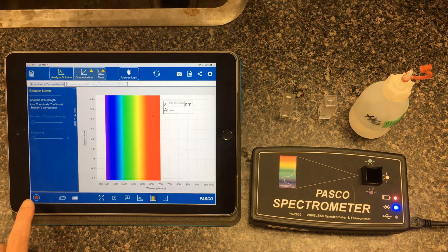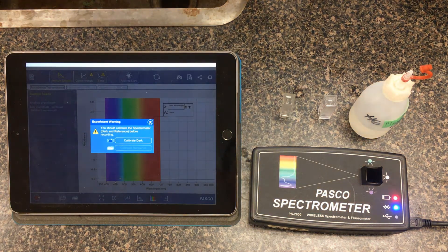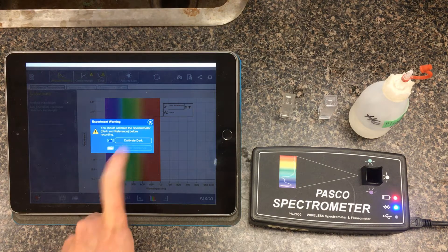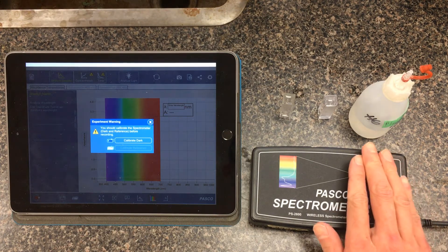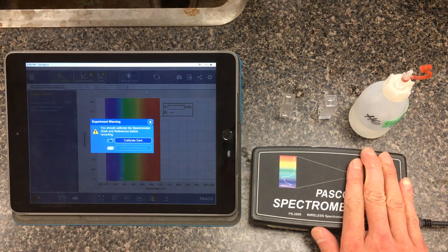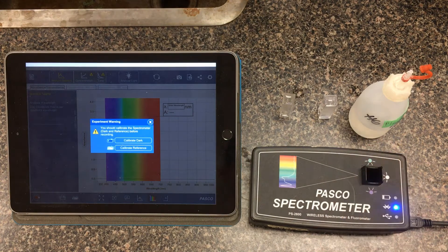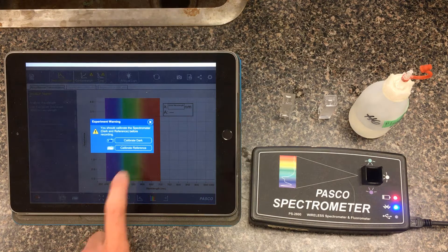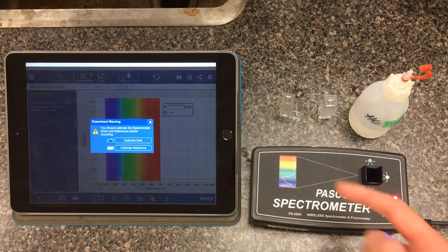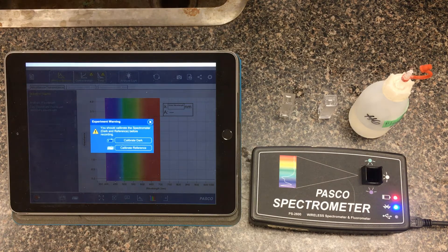We're going to start off by calibrating as we normally do — bottom left corner, press record to begin. We always want to calibrate the scale and make sure everything is zeroed properly. For calibrating dark, it should leave the light off, but if you're unsure you can block out the light. After calibrating the dark, it asks us to calibrate the reference — essentially as light travels through one centimeter of the cuvette and through the solvent, in this case water, we want to set that to zero so it's automatically subtracted from our solution.